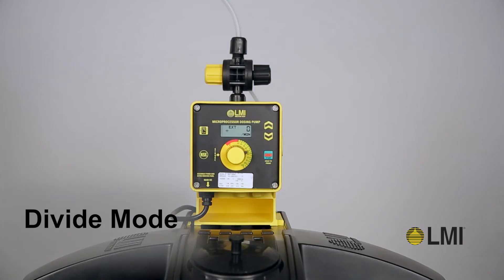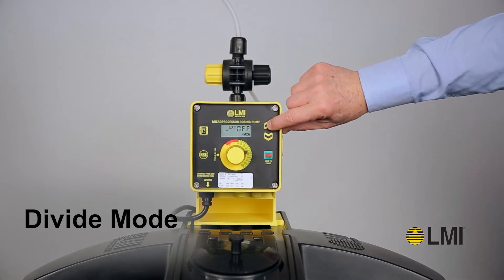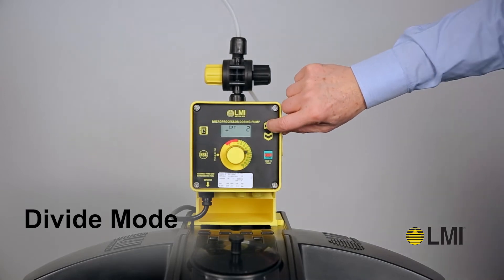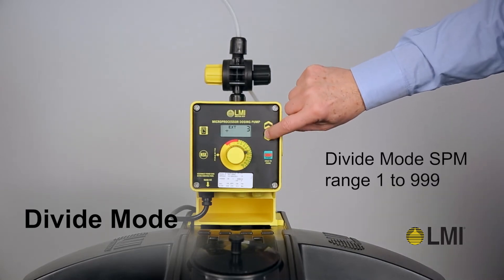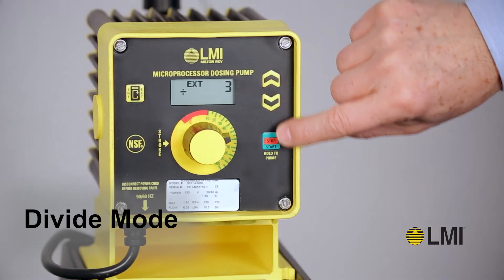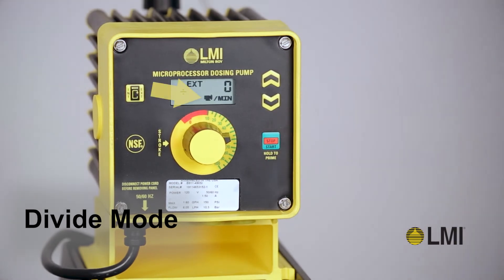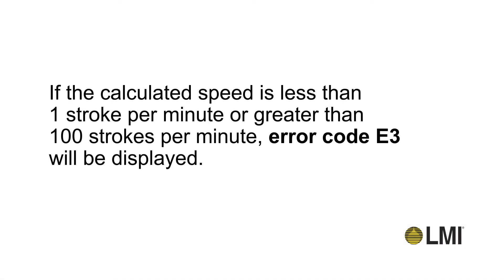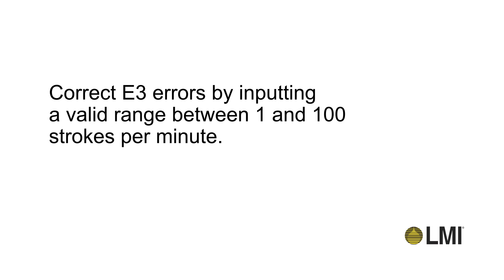When in Divide mode, use the Up and Down keys to change the value. The range in Divide mode is from 1 to 999. Press the Start-Stop key to start the pump — the pump symbol appears on the screen. The pump is now ready to receive external signals. If the calculated speed is less than 1 stroke per minute or greater than 100 strokes per minute, an E3 error code will be displayed. Correct E3 errors by inputting a valid range between 1 and 100 strokes per minute.